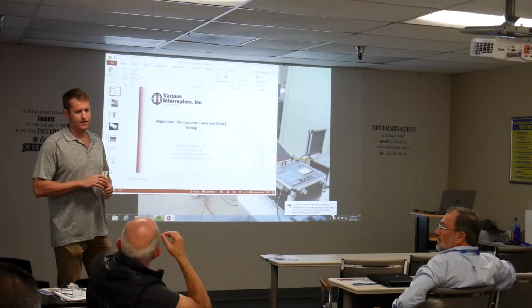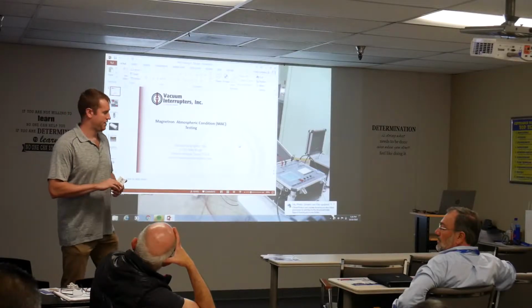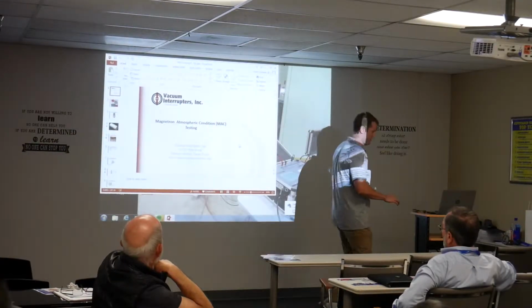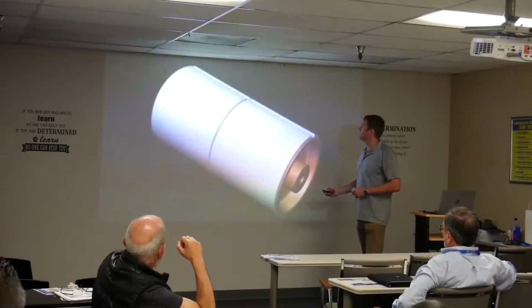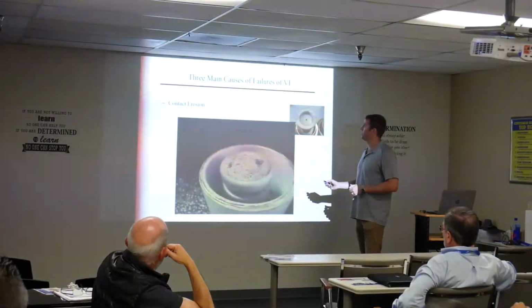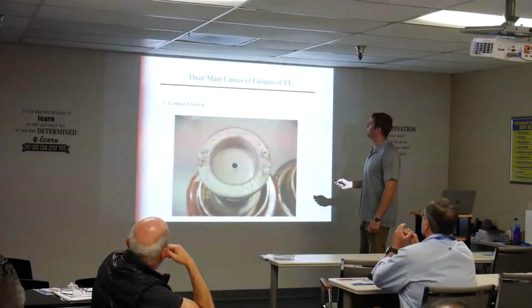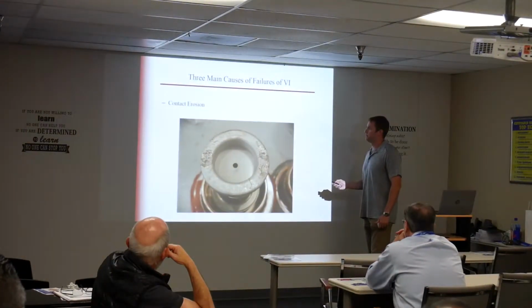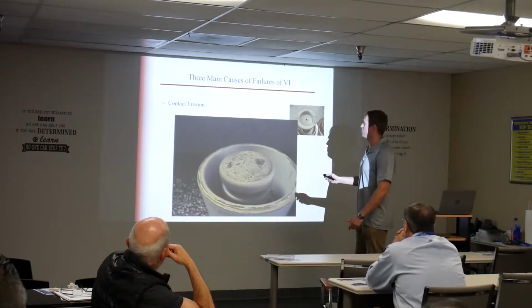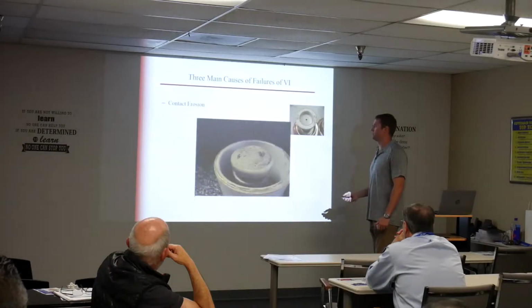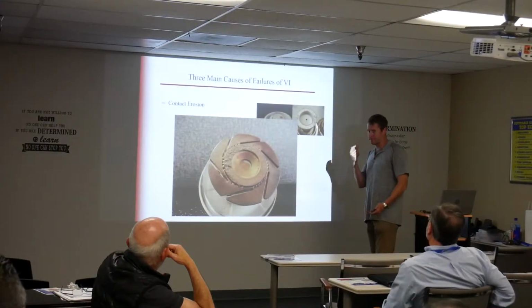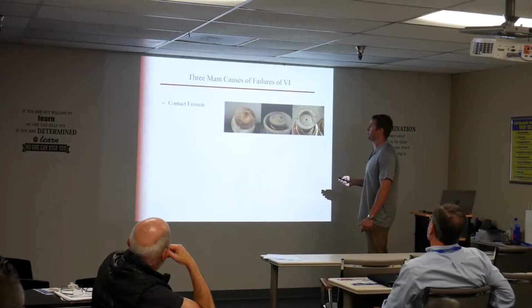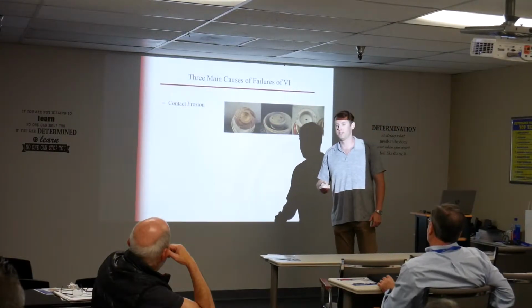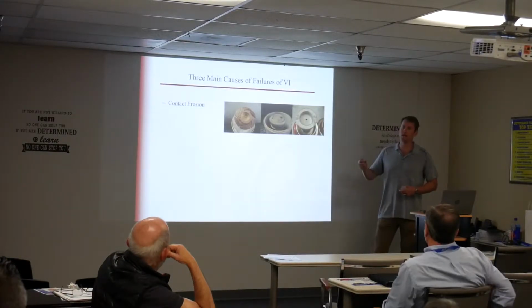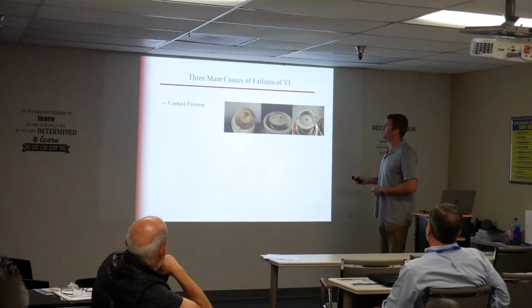Typically with interrupters, if the contacts are kept closed all the time, like in a 20-year lifespan, unless they're being cycled once a month, they don't wear much at all, right? So yeah, I don't know if you saw it, the three main causes of failure of vacuum interrupters. But you're right, most of them are closed the majority of their life, so they don't have much wear. This would be something that's using a repetitive duty, like a motor starter or an arc furnace. I've been to some research facilities that are running experiments, but yeah, most of them are closed. Most operations are done during maintenance, when the testing companies come out and operate it. So yeah, exactly. Most of them don't fail because of this.